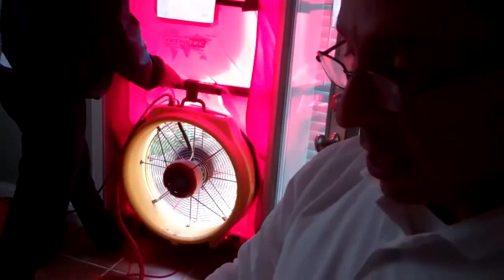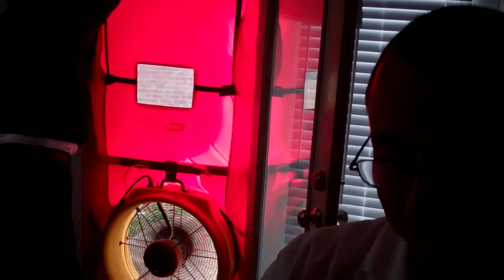So we're at 41.7. And we have a flow rate of CFMs of 4,825. Here we go. It's starting to pressurize now. We're at 44. This could not get to 50 pascals of pressure in the house, but it extrapolated it again for us at 4,935 CFM at 50 pascals.